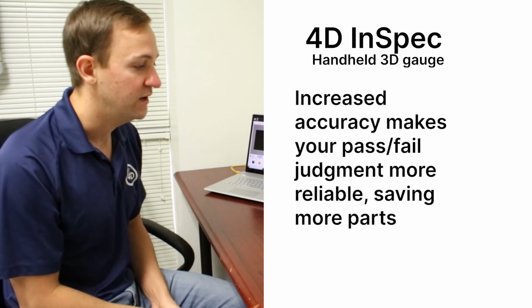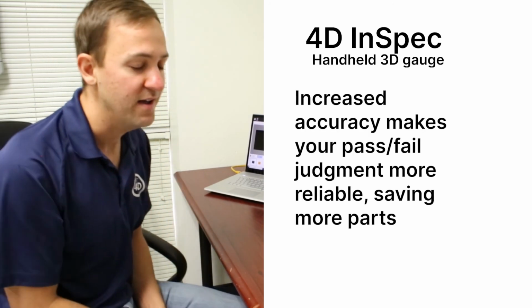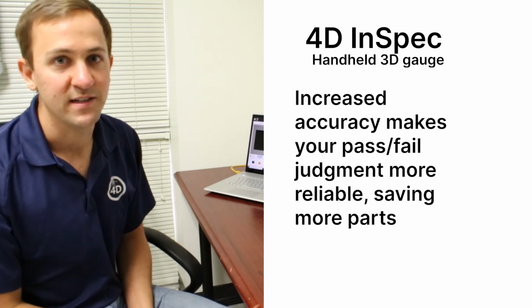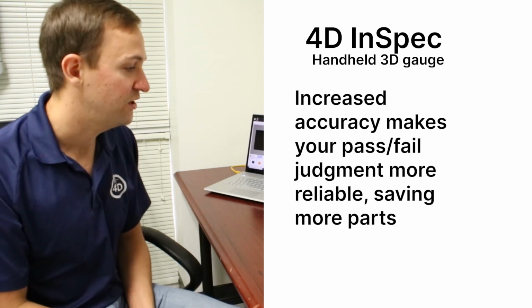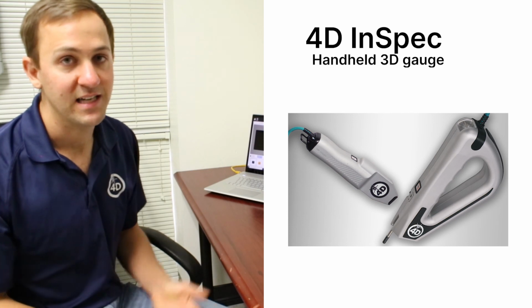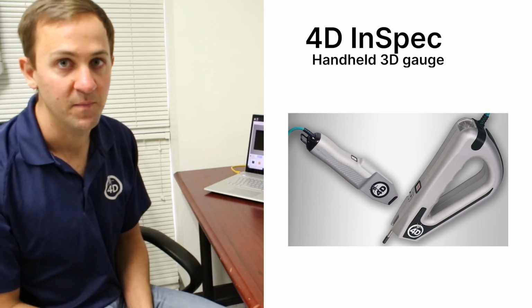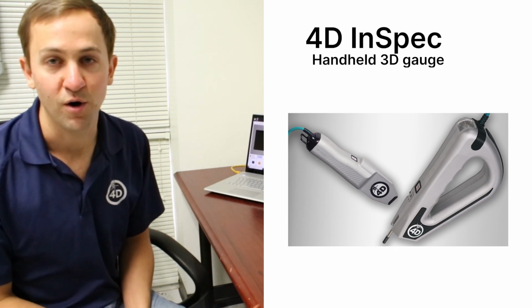Let's say, for example, I used my results from the stylus. I measured around 50 or 60 microns, and now this part is actually more around 90 microns, and the spec is 75 microns. I could have just passed the part that actually failed.